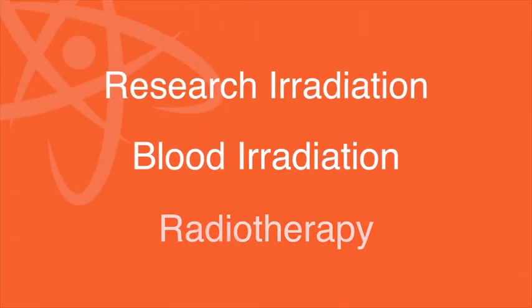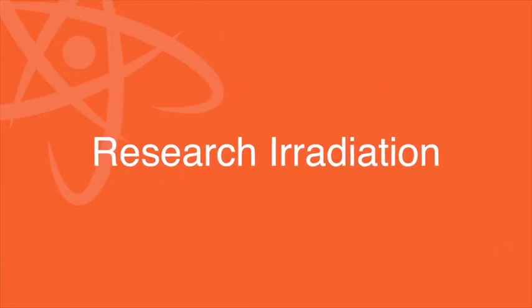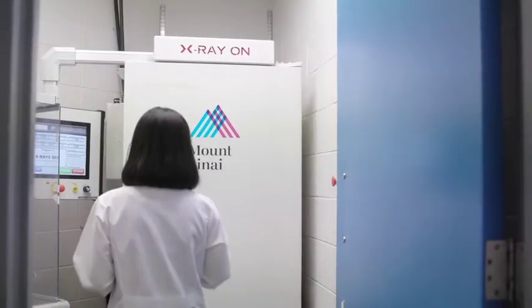One of the other residual benefits of working with ORS and replacing the technology is this: when you have the cesium source, you are required to meet certain federal regulations that are both cumbersome and expensive. Viable alternatives to cesium irradiators are now available and have been proven to be comparable or even more effective for research in some cases. The X-ray irradiator is a little bit easier to use — we can do it ourselves without someone necessarily setting the machine up, because the security is a little bit easier. With a cesium irradiator, the irradiation source decays over time, so settings must be changed each use, adding a variable into experimental design. With X-ray, it can always be the same and standardized, making it easier to get reliable data.